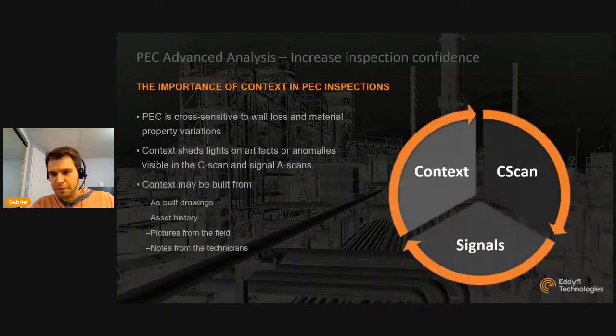We'll discuss the importance of context in PEC inspections. So pulse eddy current is sensitive to three parameters: the wall thickness of the component we're inspecting, the conductivity of the component, and the permeability of the component. For a traditional PEC inspection, it is assumed that permeability and conductivity are constant throughout the component, which is true most of the time. In some cases, there are variations of conductivity, permeability, or interfering components that will affect the PEC signals. And this is why it's important to look at the context surrounding the PEC inspection.